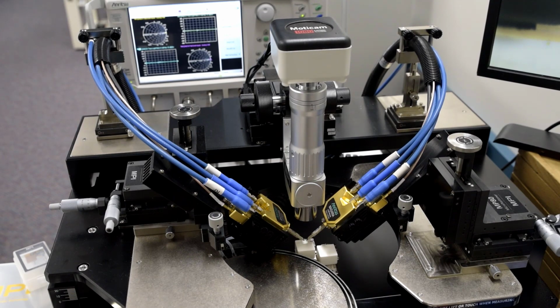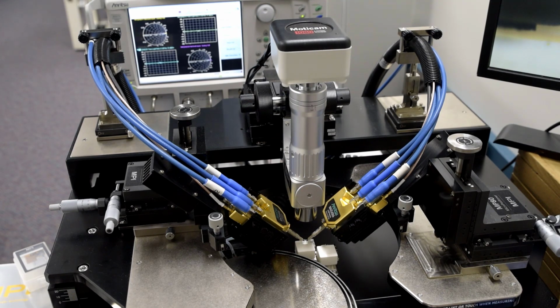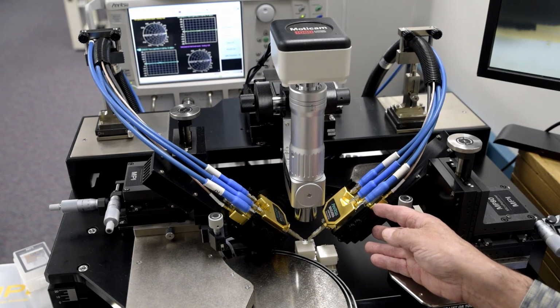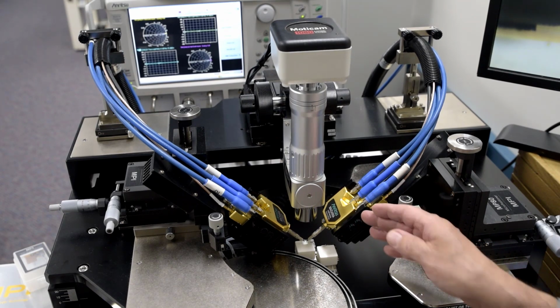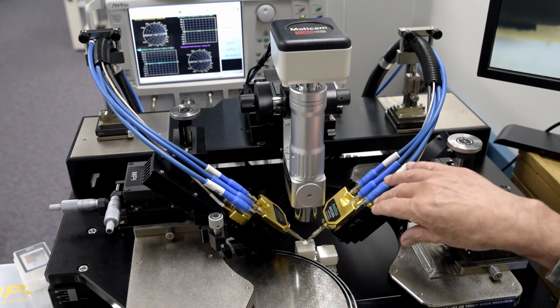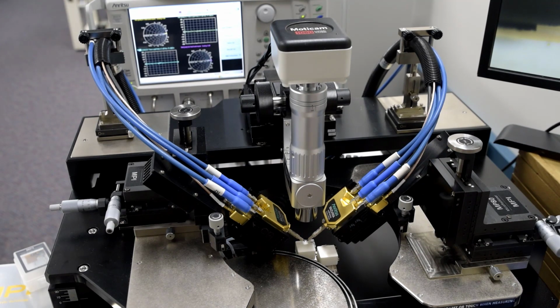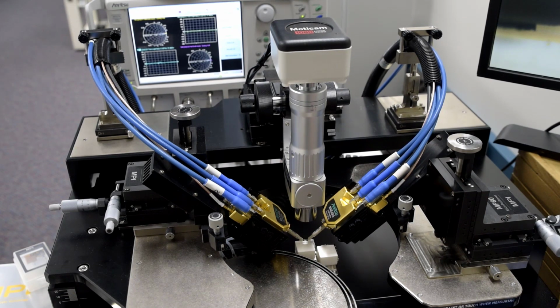So here we have the VectorStar 220 GHz broadband system installed on the MPI TS200 probe station, and we're using the MPI brackets that mount the module onto the MP80 positioner. And connected to the modules are the probes, the T220 probes. So we are set up for a probing measurement from 70 kilohertz to 220 gigahertz.